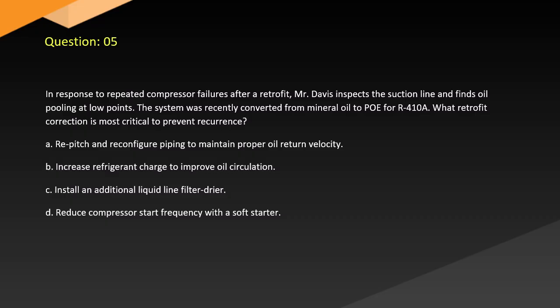Question 5. In response to repeated compressor failures after a retrofit, Mr. Davis inspects the suction line and finds oil pooling at low points. The system was recently converted from mineral oil to POE for R410A. What retrofit correction is most critical to prevent recurrence?